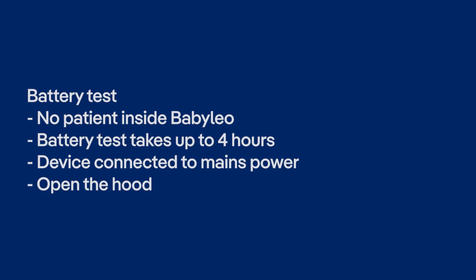Please keep in mind that the incubator must not be in use, that is, a patient must not be inside Babyleo during the battery test. The battery test takes up to 4 hours. The device must be connected to mains power.